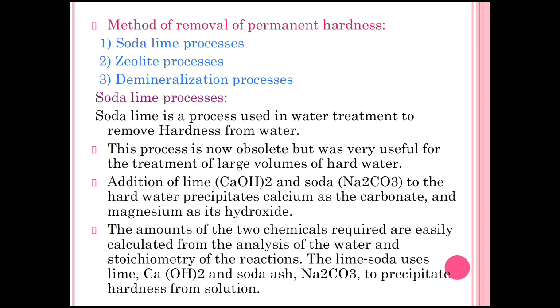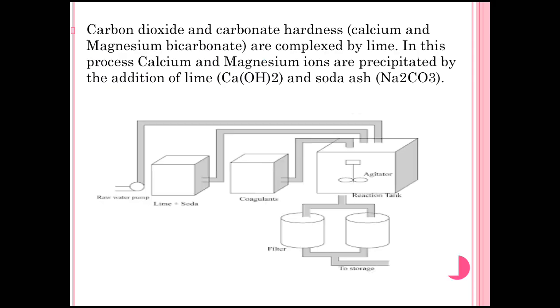The lime-soda process uses lime (Ca(OH)₂) and Na₂CO₃ to precipitate hardness from the solution. We add the two chemicals — soda and lime — to the water. Calcium hydroxide complexes with the carbonate hardness (calcium and magnesium bicarbonate), and calcium and magnesium ions are precipitated by the addition of lime and soda.